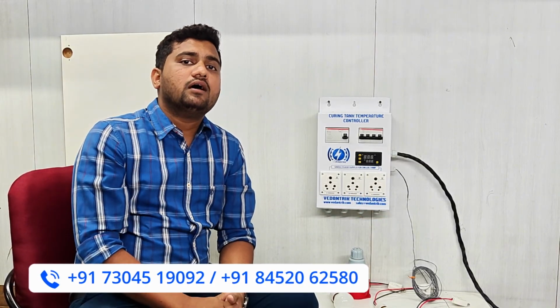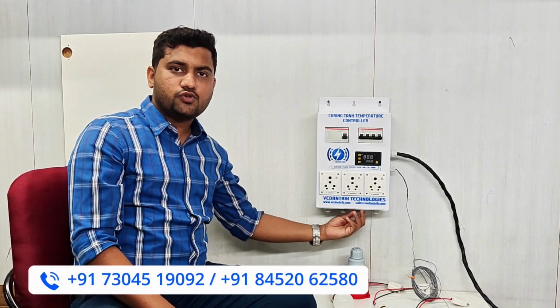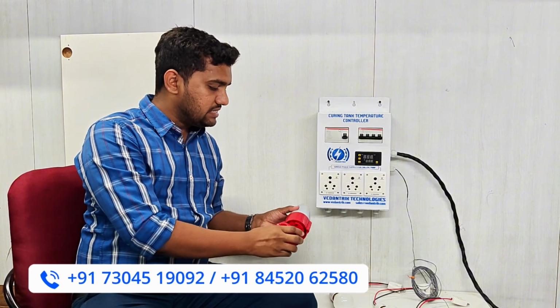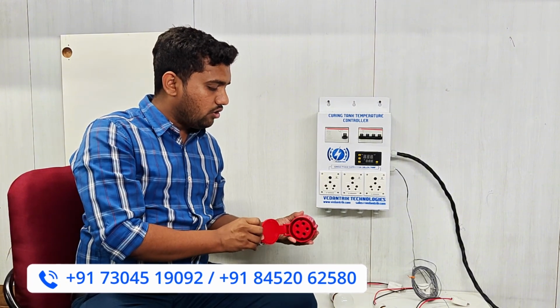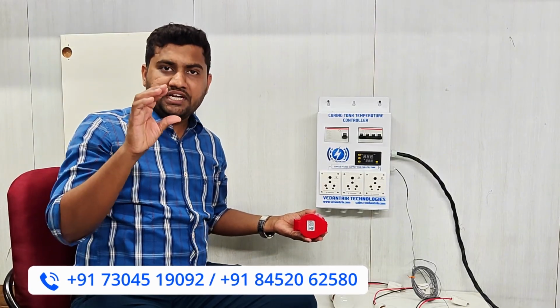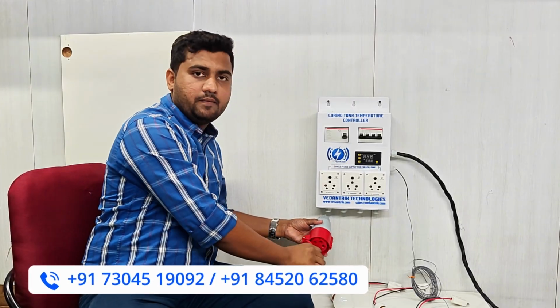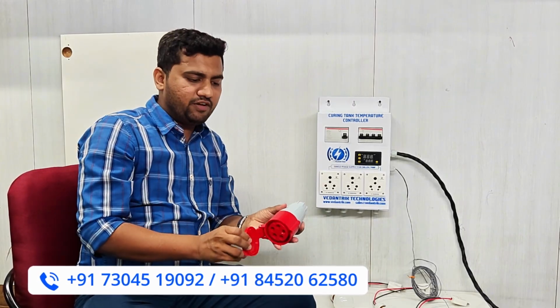But suppose if you are buying our 3-phase heater, for 3-phase heater there is a gland given over here. From that gland this type of connector will come out, and your heater will have 5 core wire, and you can see this is a high voltage or high current socket. It is also 5 core. So your 5 core heater will already have this kind of male connector. So you can directly connect that 3-phase heater here by simply male female connection, right? So this is one over here.